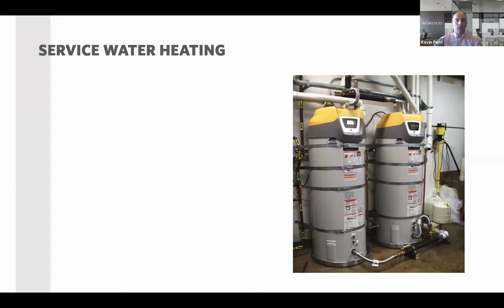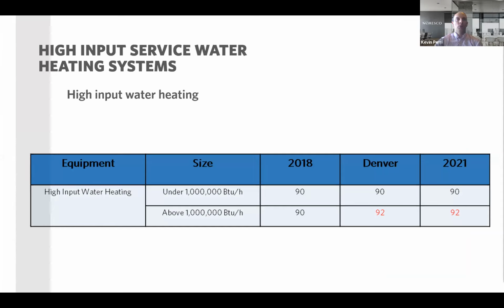So service water heating, not a whole lot has changed in that section. This is very quick, I think only 3 or 4 slides, and we'll get into it. 2021 has changed the service water heating efficiency for high input heating. Water heaters that are high input, so that's above 1 million BTU per hour, now require an efficiency of 92. This is new to the 2021 code cycle, but as you can see from this chart, if you're familiar with the city and county of Denver, they actually adopted this the previous year. So if you're outside of the city and county of Denver and other parts of the state, then this would be new. And it wasn't a big change. It went from 90 to 92% AFUE.